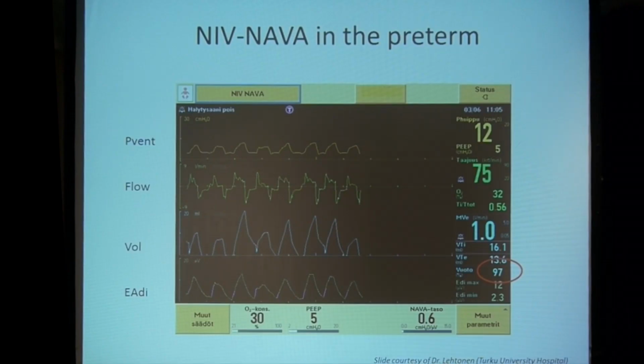This is what non-invasive NAVA looks like in a preterm baby, and I think Howard's going to show a lot more about that. But you can just see here that when the leak in this case was 97%, despite that huge leak, we were still able to maintain the synchrony, both in terms of the timing of when the ventilator starts, when it cycles off, and also that smaller efforts give smaller breaths, larger efforts give larger breaths. So we have the synchrony in timing and in proportionality.